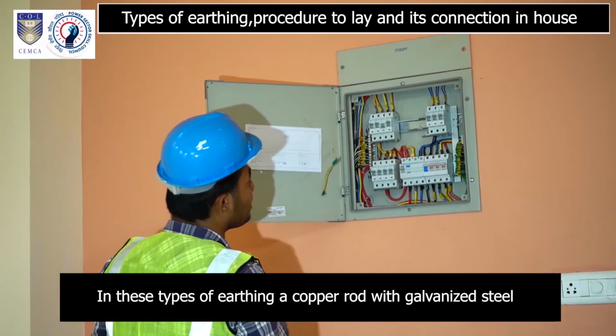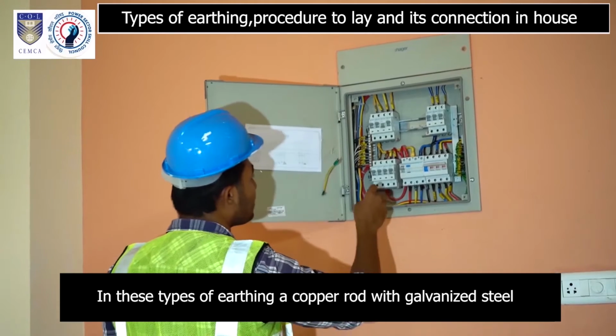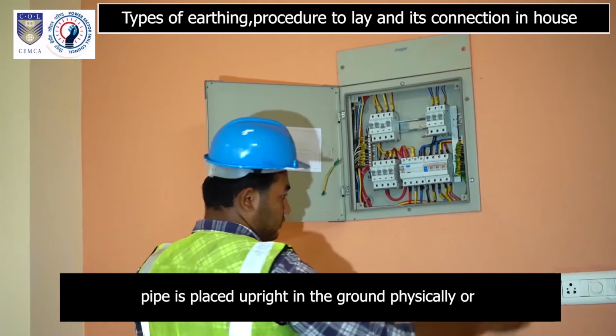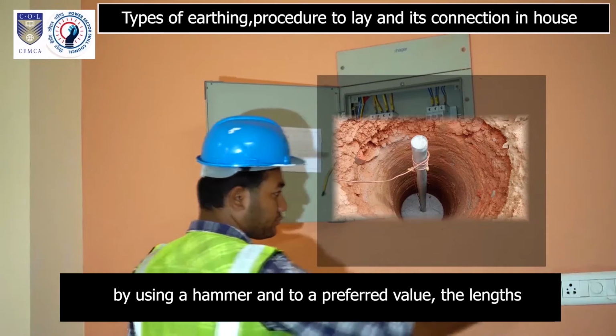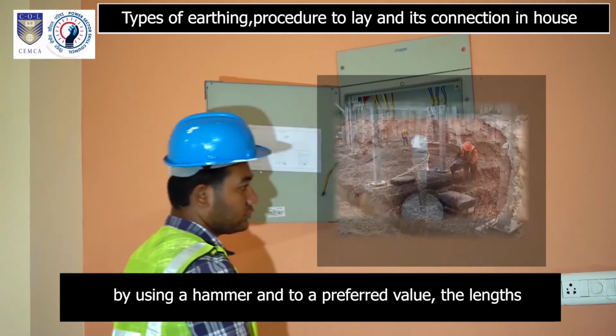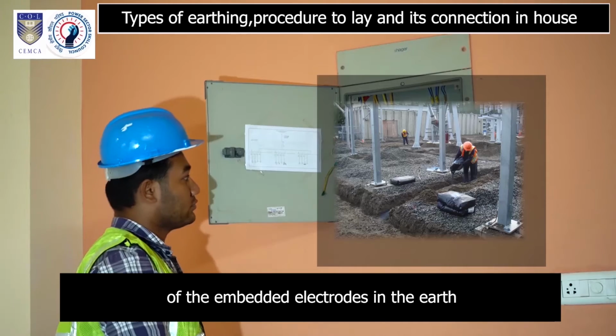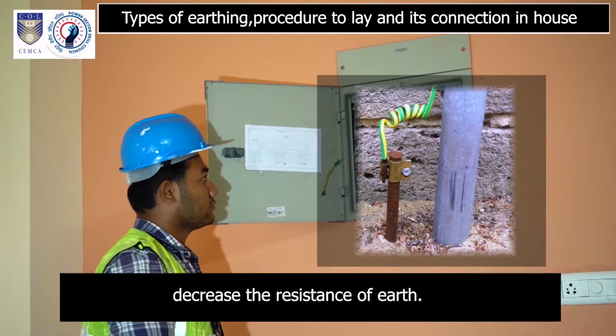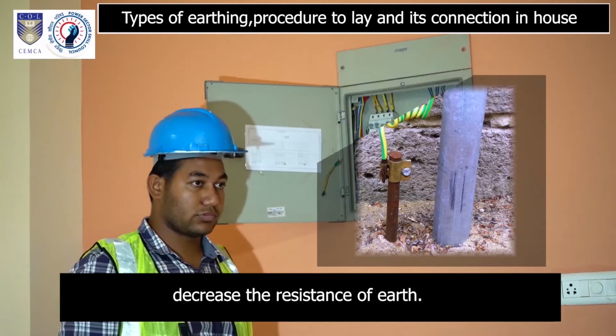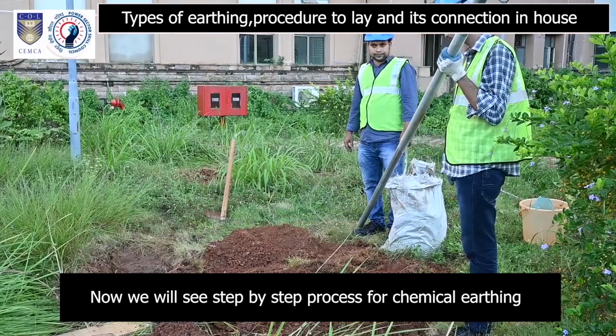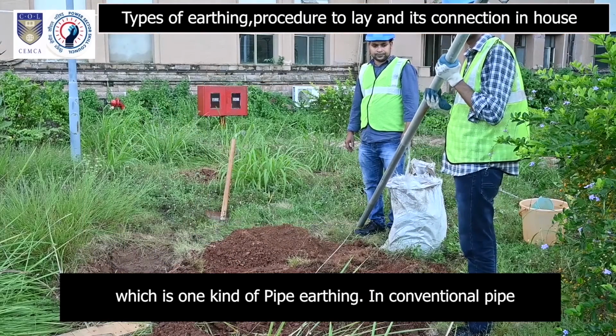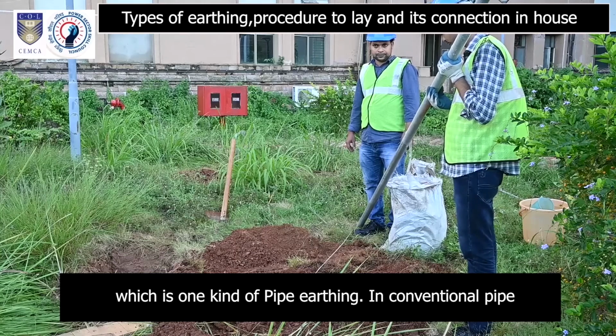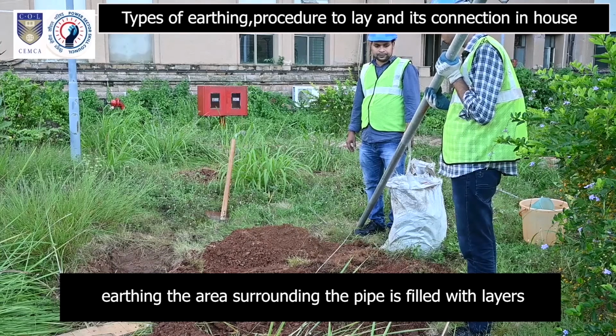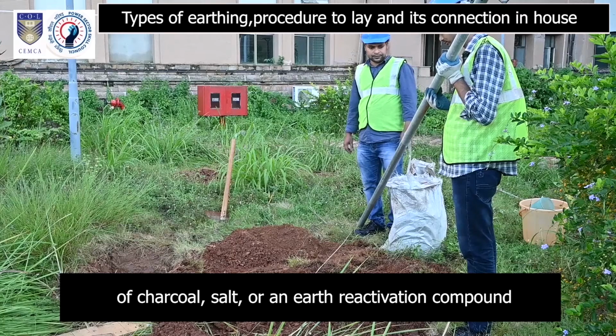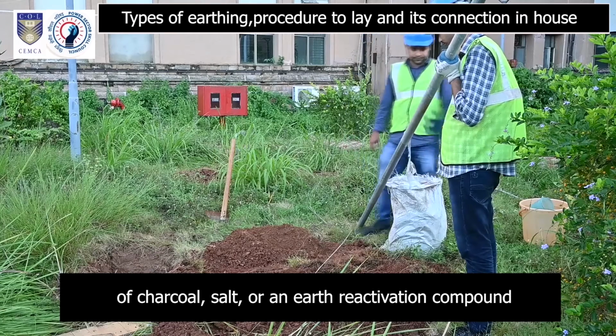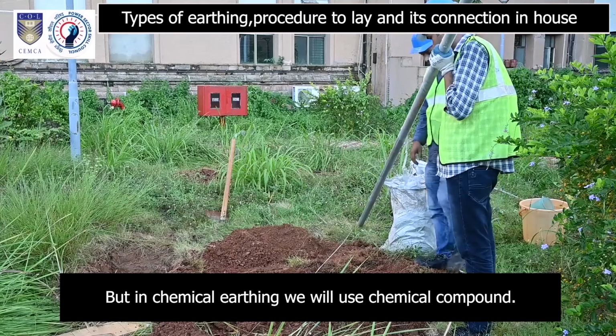3. Rod earthing. In this type of earthing, a copper rod with a galvanized steel pipe is placed upright in the ground physically or by using a hammer, to a preferred depth. The length of the embedded electrodes in the earth decreases the resistance of earth. Now we will see the step-by-step process for chemical earthing, which is one kind of pipe earthing. In conventional pipe earthing, the area surrounding the pipe is filled with layers of charcoal, salt, or an earth reactivation compound. But in chemical earthing, we will use a chemical compound.